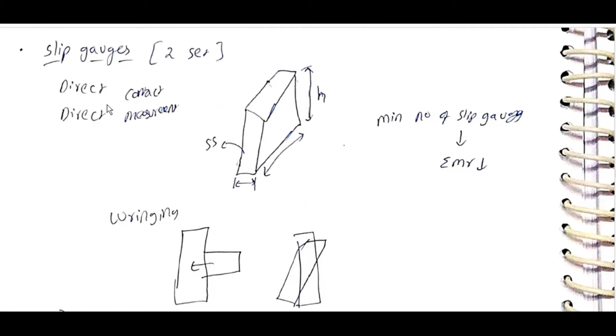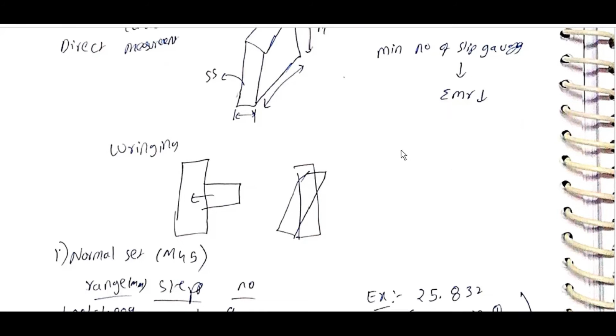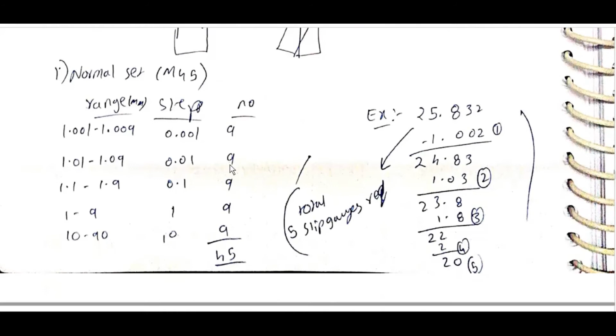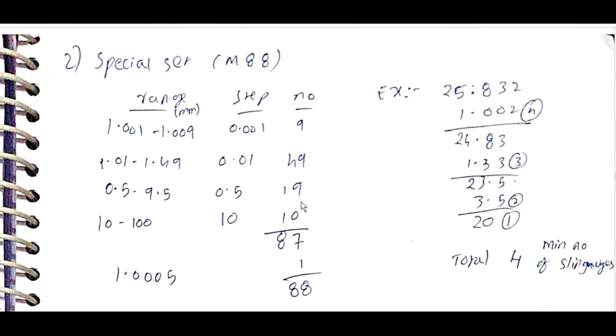Slip gauges: two sets, direct contact, direct measurement. The minimum number of slip gauges should be used, so the sum of errors decreases. With wringing, the normal set M45 combinations can be added to get the required number. The special set M88 is also available, and these can be added to get the required number.